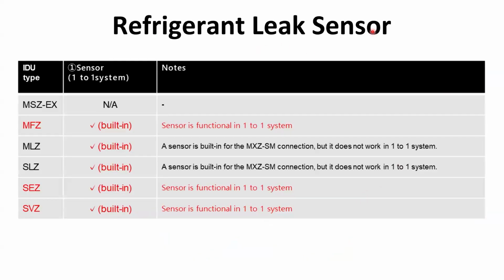Talking about the refrigerant leak sensors. So it's a good snapshot right here of what to expect if they have a sensor, if it's built in. We get quite a few questions on these: which units have the sensors, where are they located, etc. So again, here's a good screenshot about it. So the MSZ-EX is just not available. The MFZ, that's the floor unit, built in. Tells you if the sensor is functional in a one-to-one system or when it's functional, right, is what it's saying here in these notes.